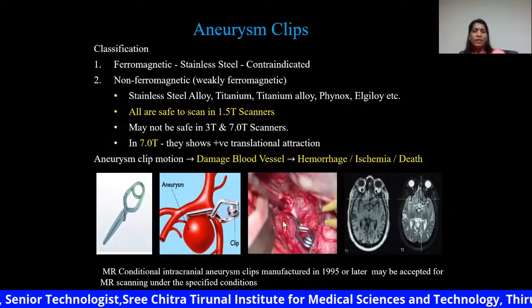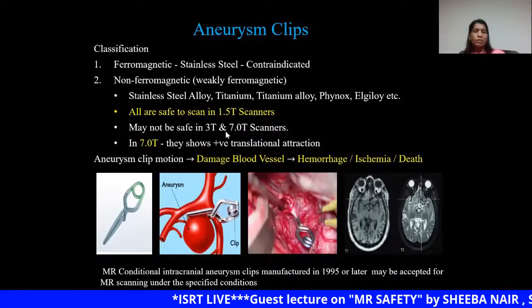But clips manufactured after 95 have been tested for MR safety, and if the manufacturer says it is safe under specific conditions, we can image such clips at 1.5 Tesla. These may not be safe in a 3T or 7 Tesla system.